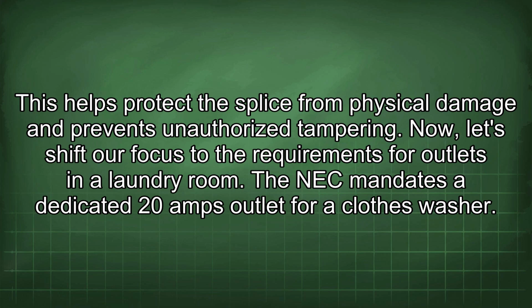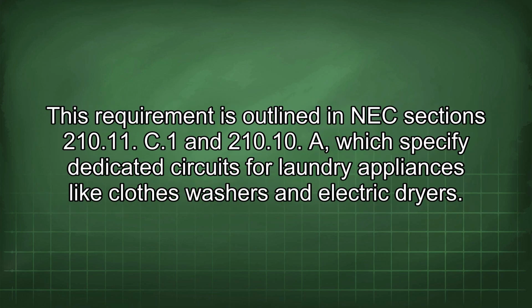Now let's shift our focus to the requirements for outlets in a laundry room. The NEC mandates a dedicated 20 amp outlet for a clothes washer. This requirement is outlined in NEC sections 210.11(C)(1) and 210.10(A), which specify dedicated circuits for laundry appliances like clothes washers and electric dryers.